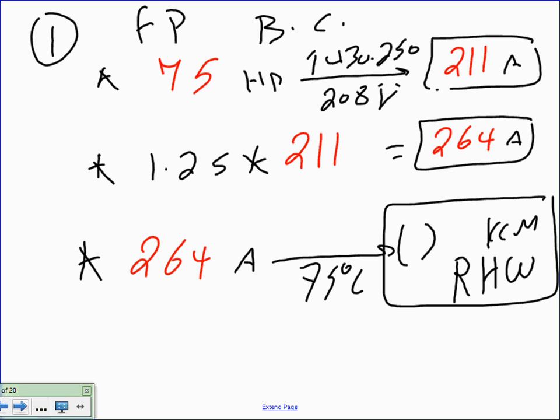With 264 amps, go to table 310.15(B)(16), and that will give you 3 conductors, 3 phase, right? Do we need a neutral for that? No, no neutral. And if you do the calculation on this one, would that be 300? Yes, thank you. 300 kcmil. That's it. No gimmicks, nothing. Branch circuit for a motor.